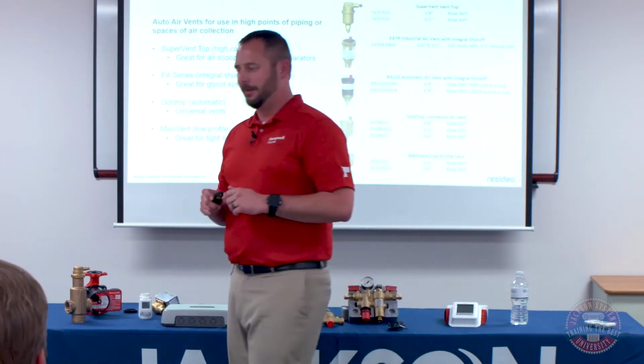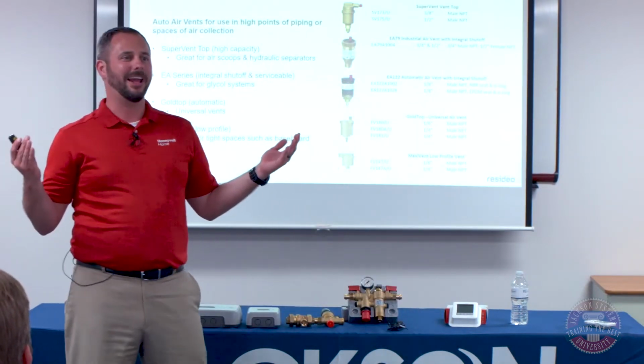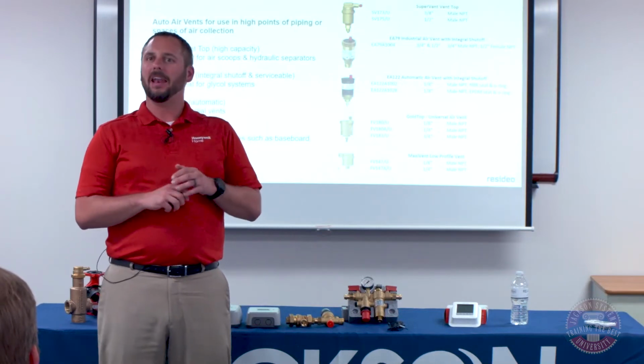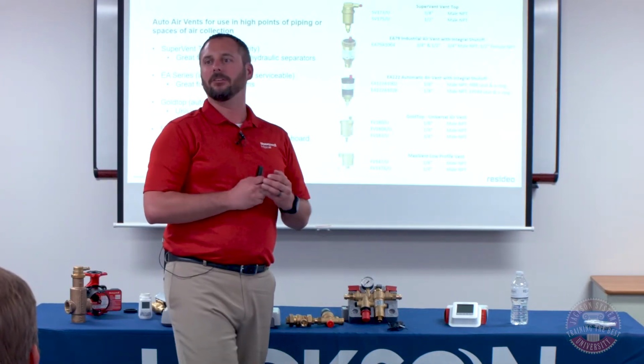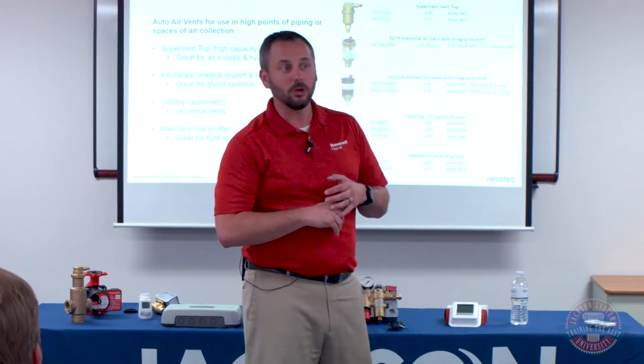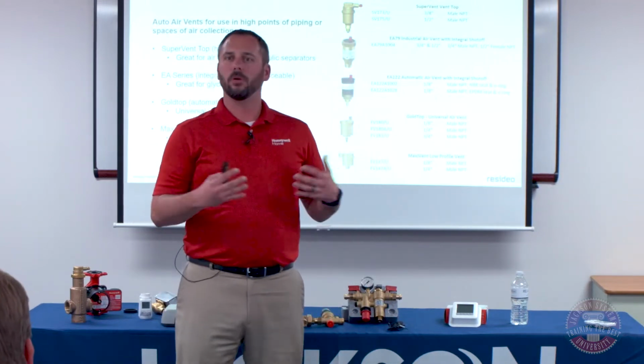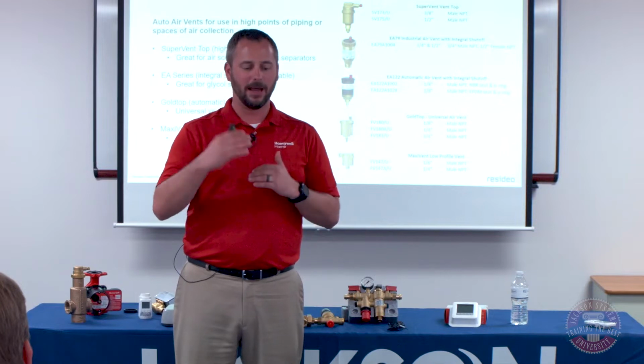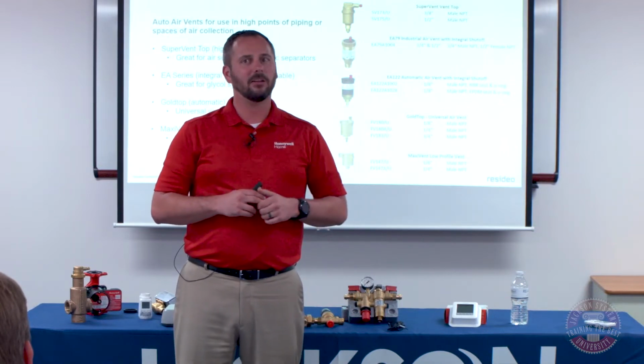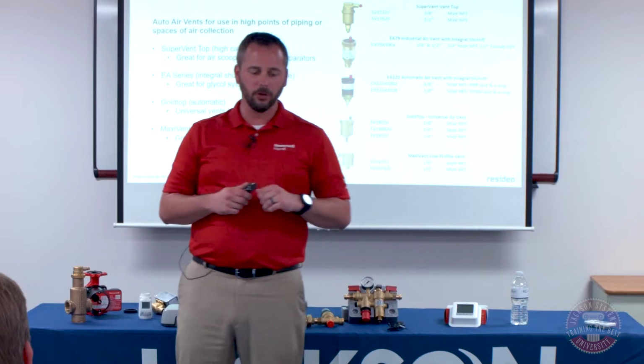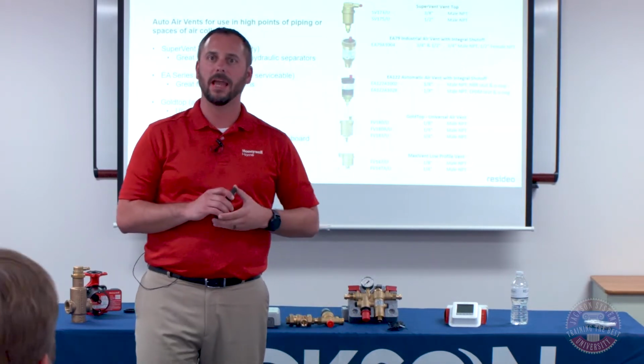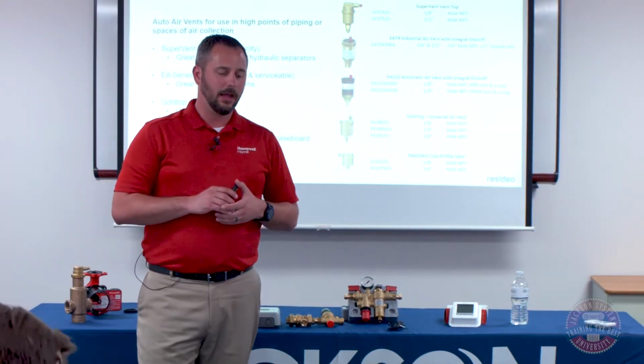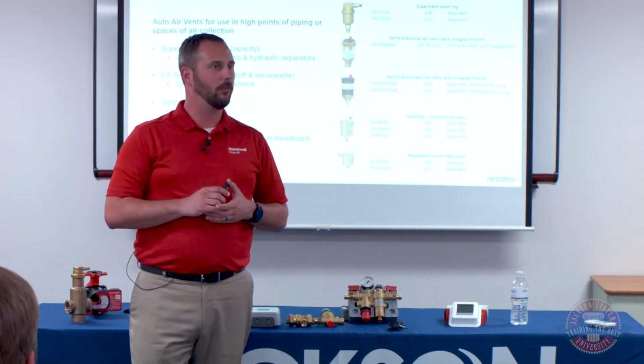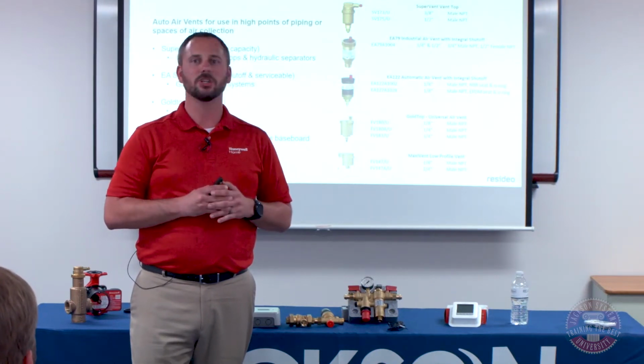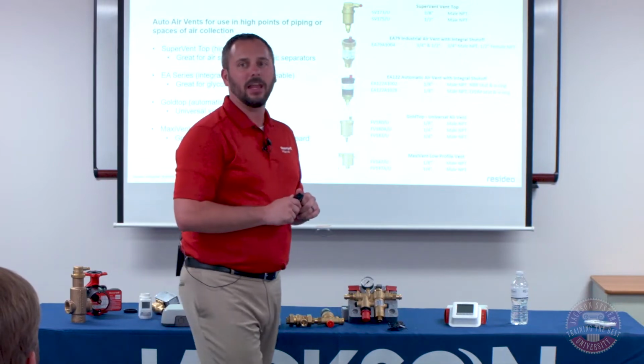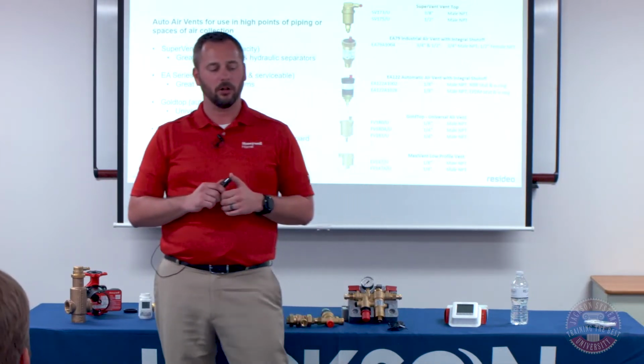So, capping out air elimination, I can't talk about air elimination without talking about air vents. We've got a lot of different air vents, and each air vent has a slightly different application and best use. So what I did is I took our portfolio of air vents and laid them out in a sheet on this page and listed where they're best used. The first is the super vent that I talked about. I talked about how we changed the design, made it a 90-degree elbow, and virtually all of our leakage issues went away. We make that same type of design in what we call our super vent top.